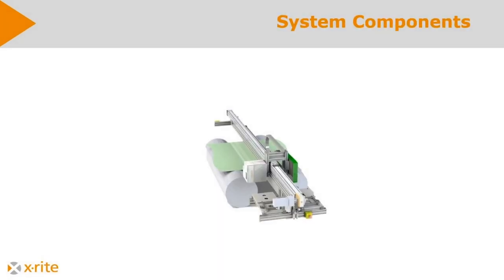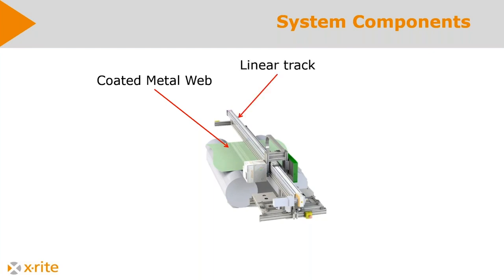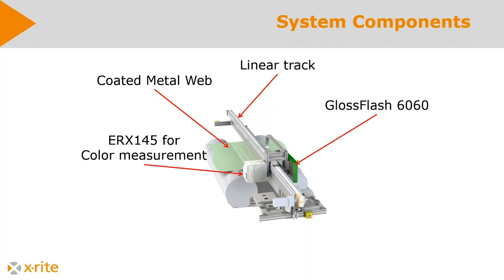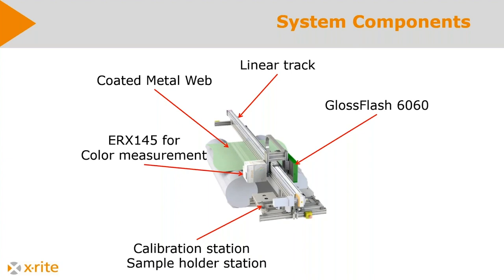Well, this was the instrument, and this is how it looks at the machine. If this is the coil on the machine, you see two rollers below. We typically have a linear track, a traversing beam, to measure left side, middle, right side. We have a measurement system on one side, the ERX 145, and if necessary, we can have a gloss flash on the other side. In the front, you see a calibration station. As I said, this instrument needs to be calibrated frequently because of the conditions we have on the production machine. So we move the instrument out and calibrate it automatically. The user has nothing to do with this. Then we continue with the measurement.